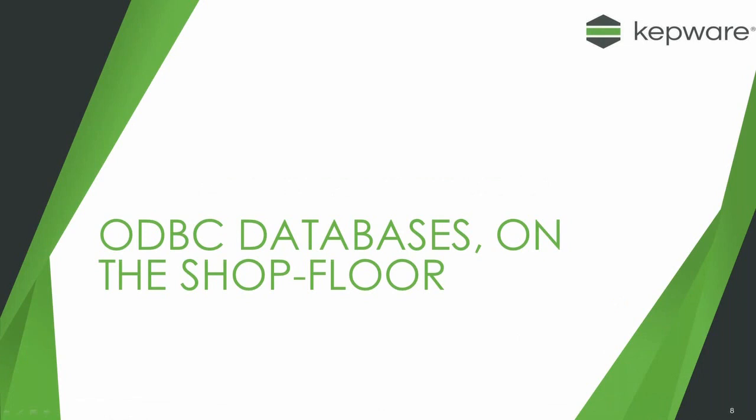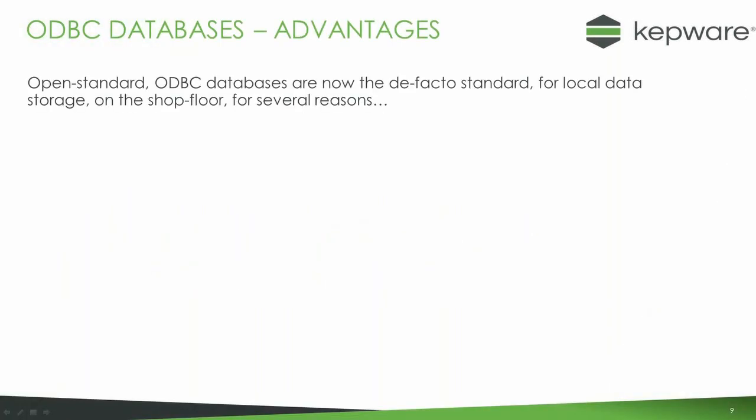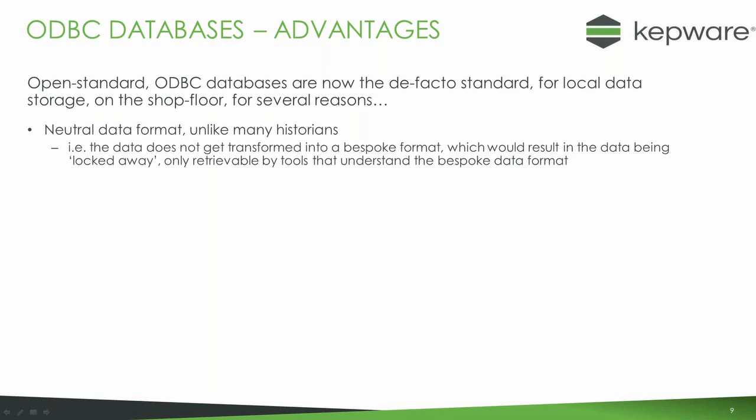Let's have a look at databases on the shop floor and why they're used. Nowadays ODBC databases are seen as the de facto standard for storage locally on the shop floor for several reasons. The first is that the data is in a neutral format. It used to be that historians were used a lot on the shop floor because storage of data was expensive, and one advantage of historians is they scrunched the data down to a small package size. But nowadays storage is cheap, so storing large databases is not as costly as it would have been.